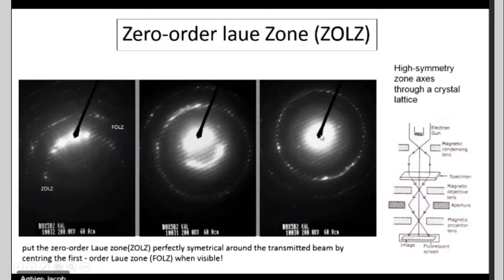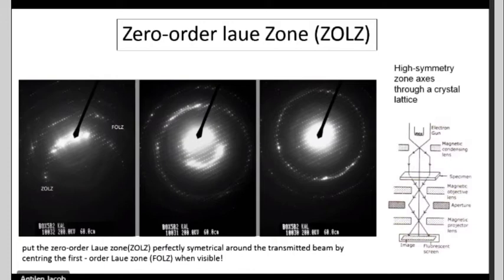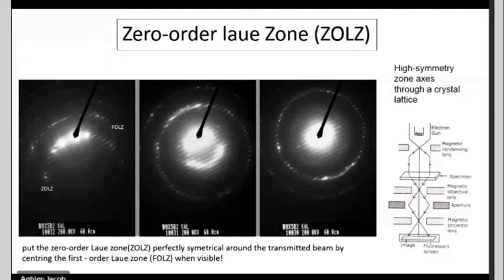If you are interested in going to a particular zone — for example, the [100] or [001] zone — you can tell the operator to tilt the sample to that zone axis and capture the diffraction image there. For ferroelectric materials, people are interested in viewing the crystal structure along a particular zone axis. If no predefined zone axis is specified, the operator goes to the zero-order Laue zone. Normally, all diffraction patterns you see are from the high-symmetry plane of the zero-order Laue zone.